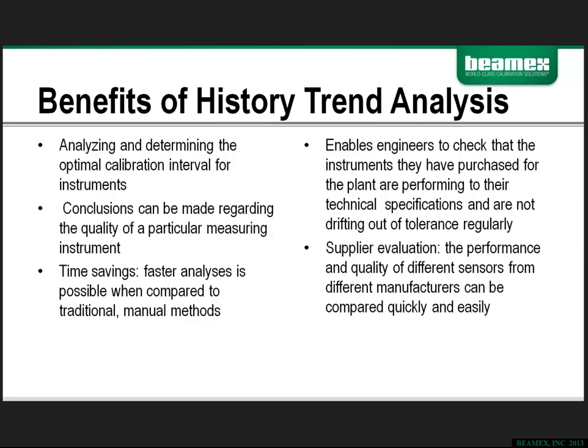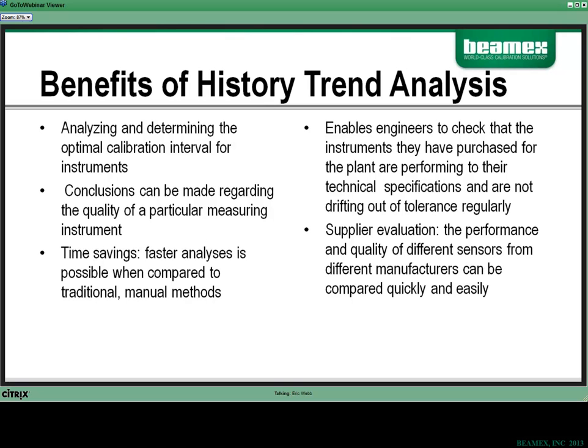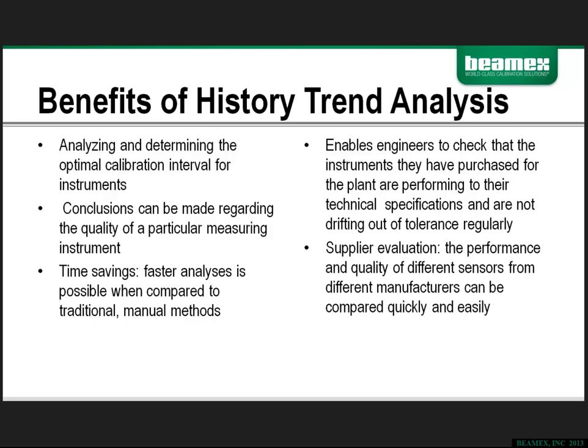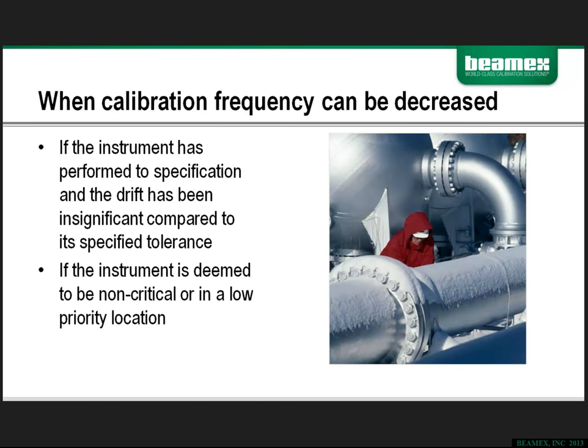So when it comes to supplier evaluation, as I stated a few minutes ago, there are many manufacturers and model numbers of sensors out there. The CMX history trend allows the engineer to compare one manufacturer model to another and determine which sensor makes the most sense for a particular position. This can save money and time that would be spent on more frequent calibrations when another particular device would allow you to expand that out. So this really gets to the heart of what our discussion is about today.